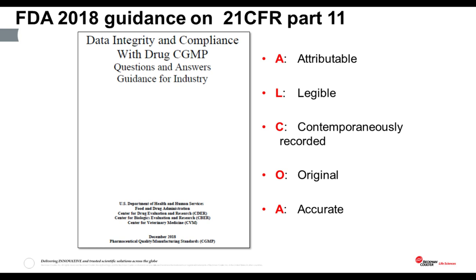In their 2018 question and answers paper on interpreting their data integrity guidance, they introduced for the first time the acronym ALCOA. In response to a question about what a good electronic record looks like, they said it should be attributable — the first A in ALCOA — to the person taking the sample. It should be legible, which implies handwriting is probably not the right way to go. It should be made contemporaneously, or at the same time the sample is taken, rather than at a later time from paper printouts. And the record should be the original record, and the data it contains should be accurate.